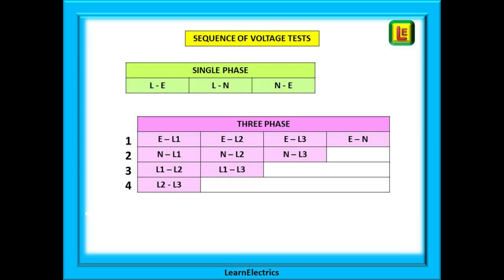How should we do these tests? Work to a system, a pattern, so that you don't miss any step out. It's easy with single phase: live to earth, live to neutral, and then neutral to earth.